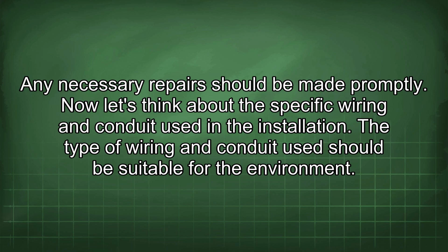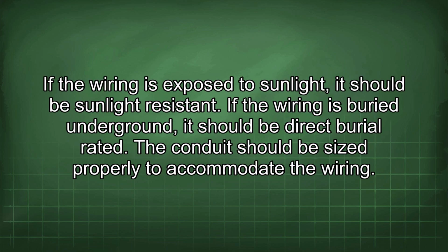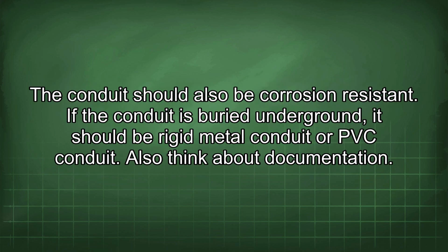Now let's think about the specific wiring and conduit used in the installation. The type of wiring and conduit used should be suitable for the environment. If the wiring is exposed to sunlight, it should be sunlight resistant. If the wiring is buried underground, it should be direct burial rated. The conduit should be sized properly to accommodate the wiring. The conduit should also be corrosion resistant. If the conduit is buried underground, it should be rigid metal conduit or PVC conduit.